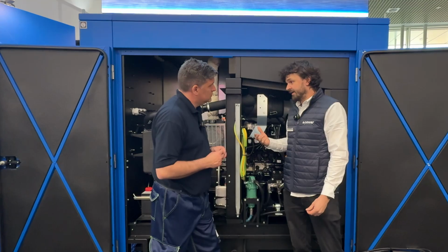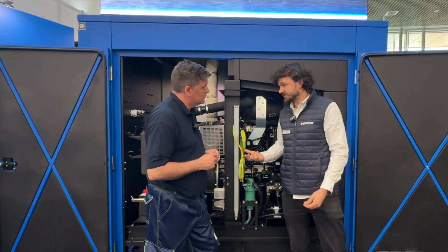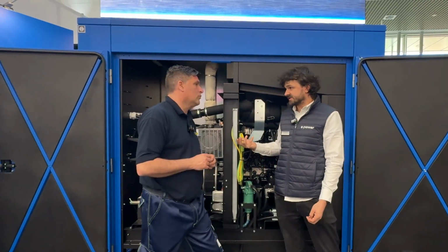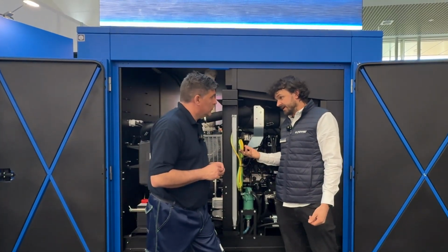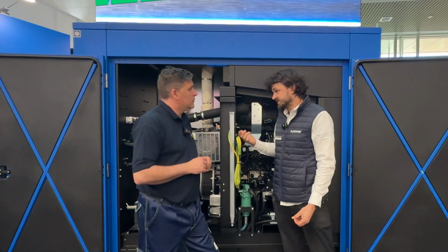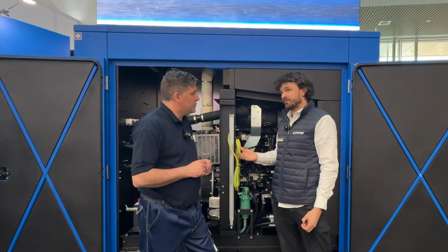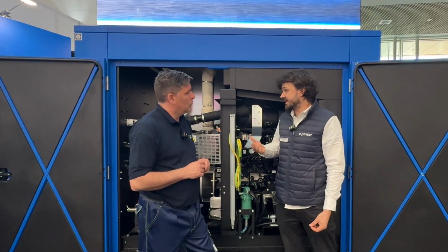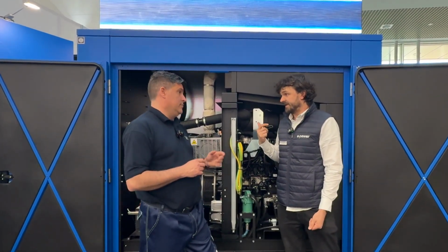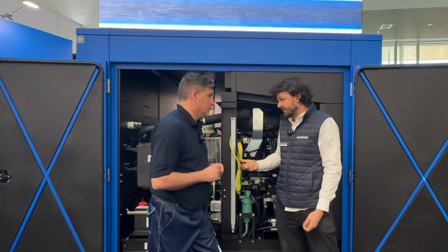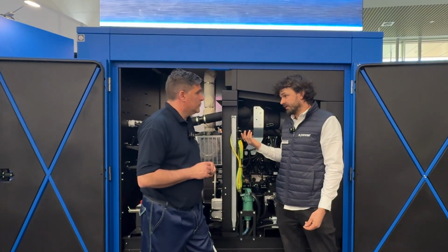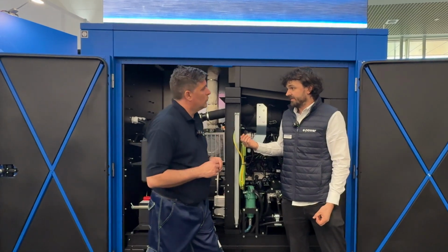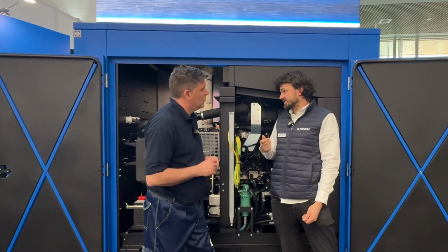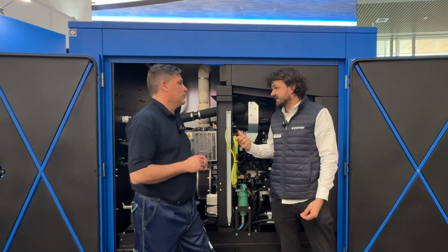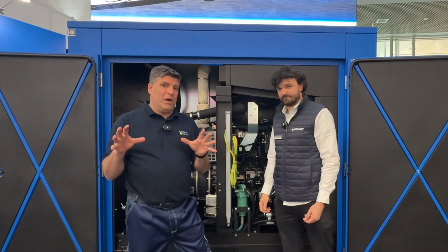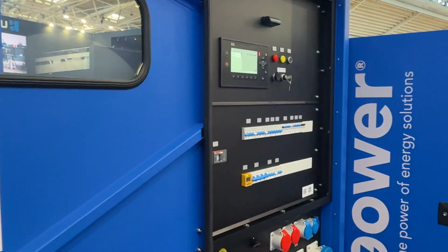If you run a generator on low load for a long time, you get wet stacking in the exhaust system, leading to extra maintenance costs and breakdowns. Especially with 200 kVA generators, AdBlue comes in too - if they don't run at a good temperature, below 20% load for instance, the exhaust doesn't reach the temperature needed to use the AdBlue, and it crystallizes. That's a big problem when you're off-grid with this sort of solution.